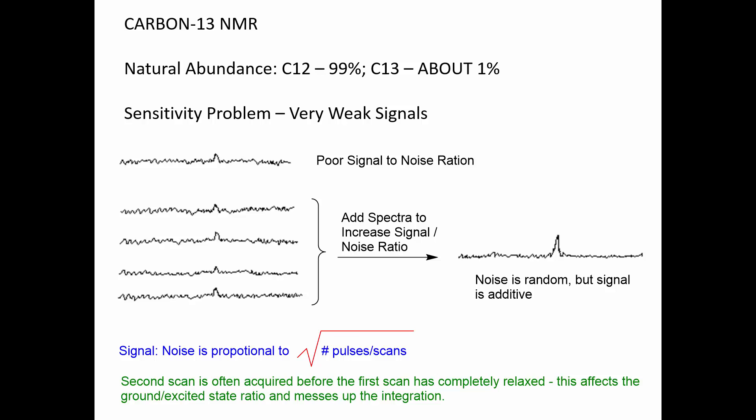An equation tells us how long we need to acquire the spectra. If we take multiple pulses or scans, the signal-to-noise ratio is proportional to the square root of the number of pulses or scans. If we take the spectrum 100 times, we can expect the signal-to-noise ratio to increase by a factor of 10.